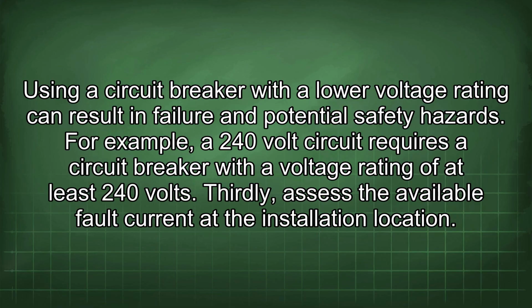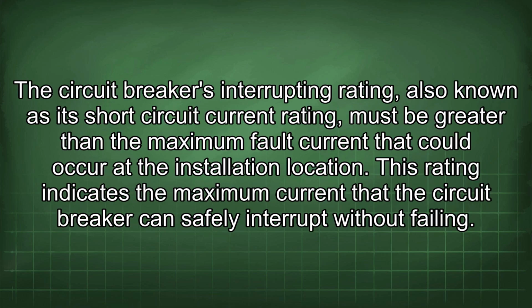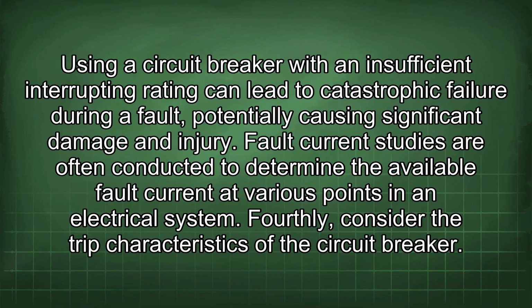Thirdly, assess the available fault current at the installation location. The circuit breaker's interrupting rating, also known as its short circuit current rating, must be greater than the maximum fault current that could occur at the installation location. This rating indicates the maximum current that the circuit breaker can safely interrupt without failing. Using a circuit breaker with an insufficient interrupting rating can lead to catastrophic failure during a fault, potentially causing significant damage and injury. Fault current studies are often conducted to determine the available fault current at various points in an electrical system. Fourthly, consider the trip characteristics of the circuit breaker.